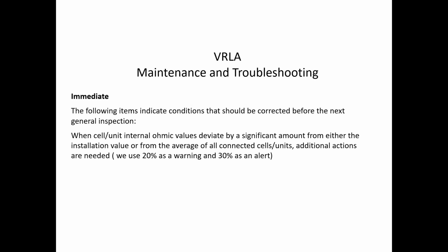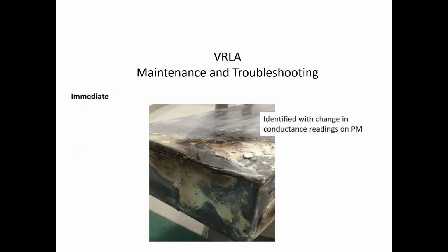Ohmic values deviate significantly. Now they have to be somewhat vague in their description of what a significant deviation value is. We use 20% from the installation or baseline as a warning and 30% as an alert. And again, that's not saying it's time to change the battery. That says, hey, it's time for further investigation. It's funny you mentioned from installation. So if you're trending it, that's the best way to do it.